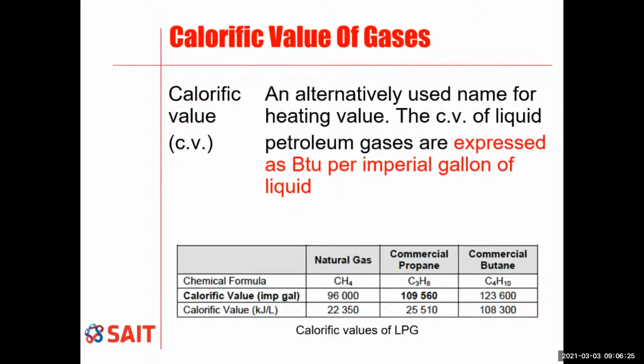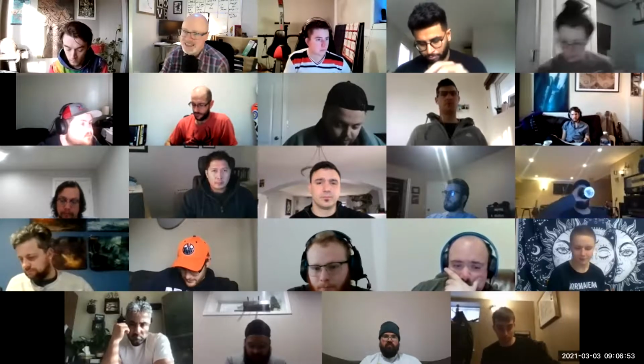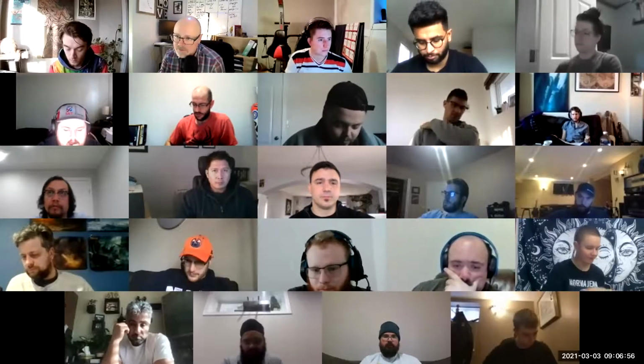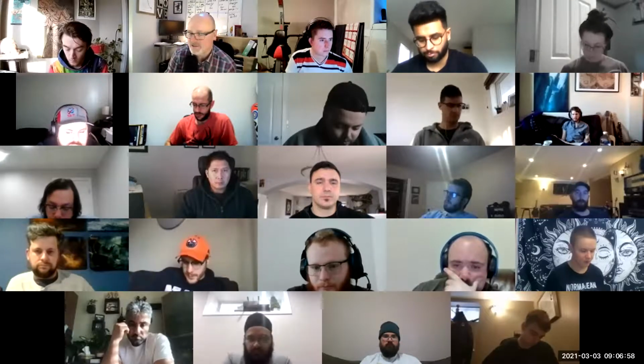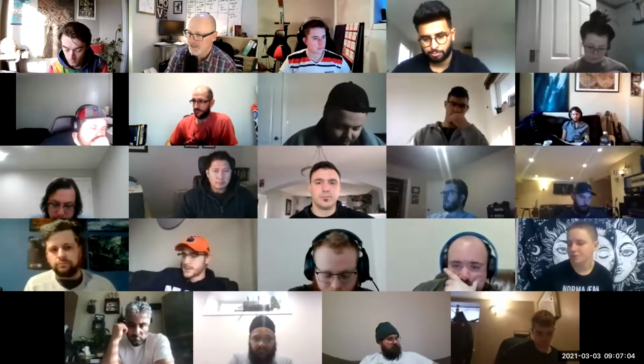So calorific value of 1 imperial gallon. It says natural gas 96,000. Now listen, we don't deal with natural gas as a liquid for the most part, so we really don't need to concern ourselves with that. We have this commercial propane, 109,560. Now here is a little bit of a difference, because did we not calculate 1 imperial gallon to be 109,000 even? Yeah. And now this is telling me it's 109,560. So there's just a slight variation in that.